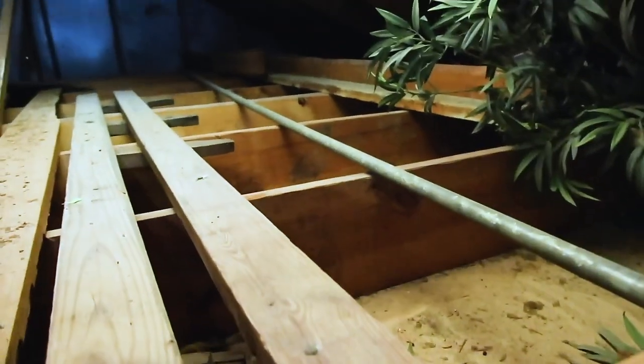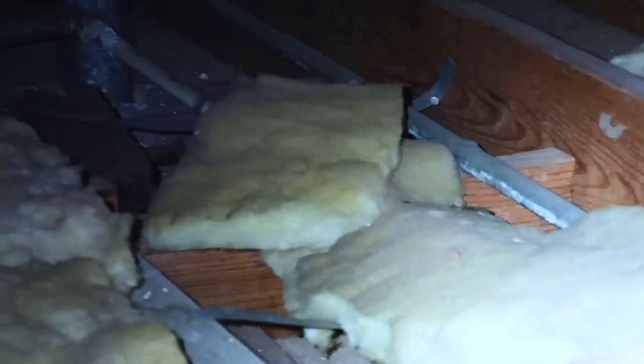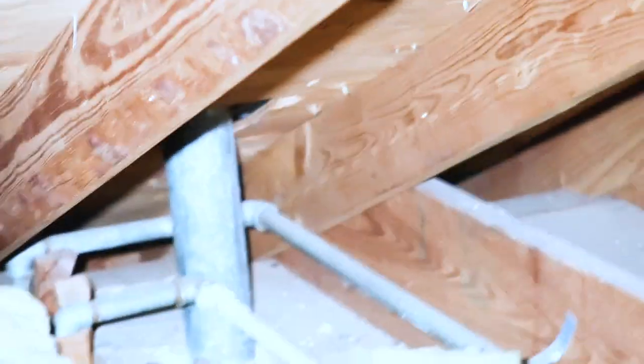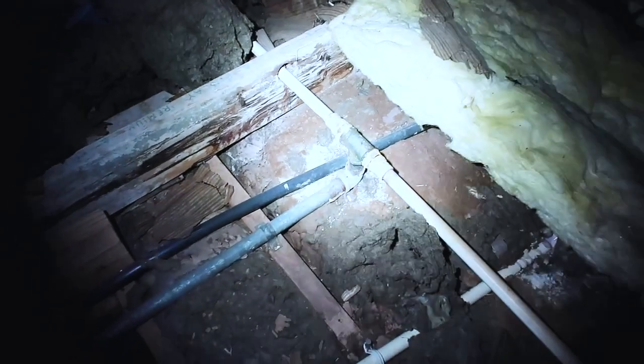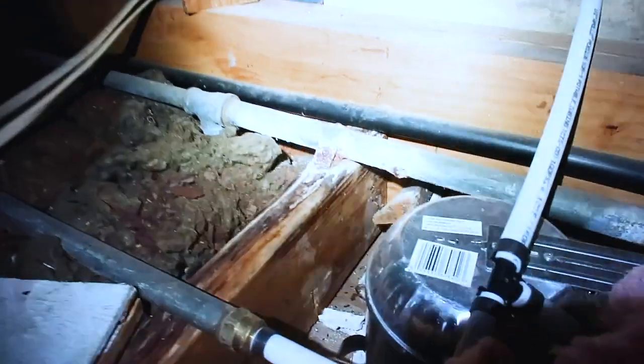Coming into the attic system, whenever you see a galvanized pipe that's been removed or replaced and is just sitting there, that should start sending warning signs. You can see where they replaced the pipe and used caulking to keep it watertight — this is one of the first signs that your galvanized water lines are compromised throughout the entire structure. You can see previous leaking running across the top, pinholes forming, galvanized lines rusting and corroding, and a pinhole leak right there. Galvanized end of life — they need to be replaced to prevent any future damage to the structure.